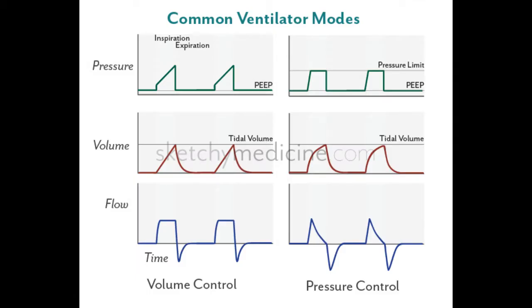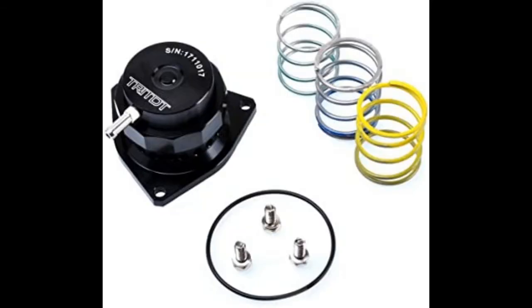I did some search online on ventilators, and the two most important things in a ventilator came up to be the tidal volume, which is a kind of pulse width of the airflow, and then the rate, which is the number of breaths per minute. I'm not a doctor, so I might not know the exact terminologies, but this is what I found. In a medical ventilator, the tidal volume is calculated in milliliter per kilogram or cubic centimeter per kilogram. So this is the reason why we cannot use an off-the-shelf blow-off valve used in cars.